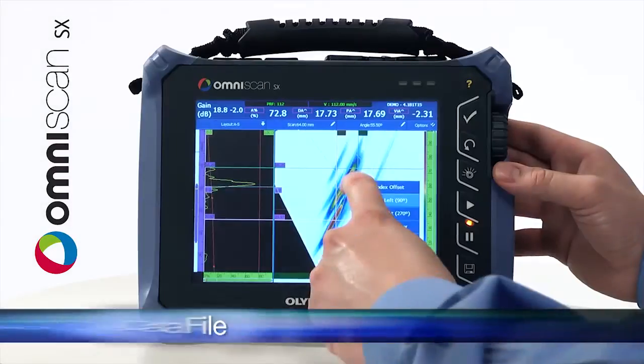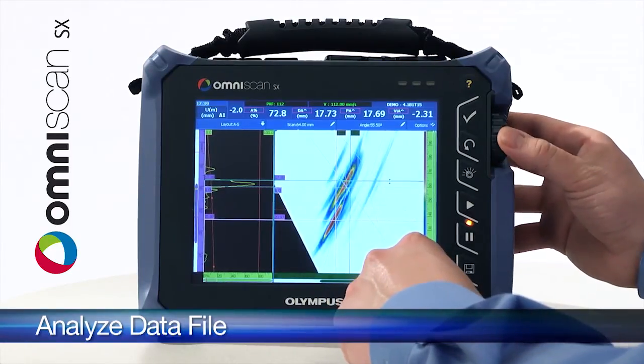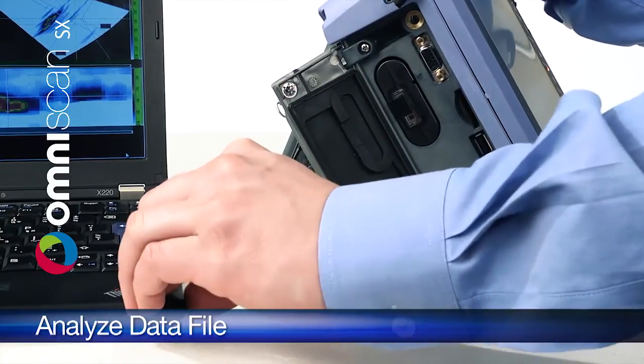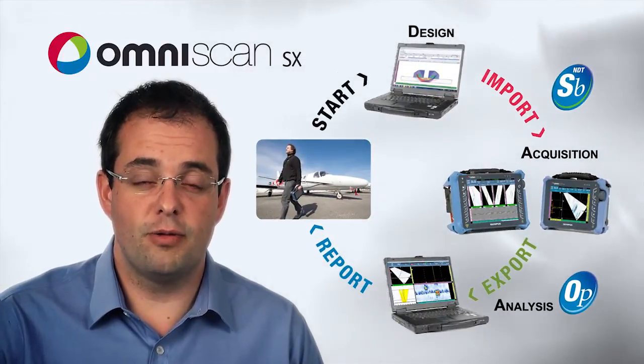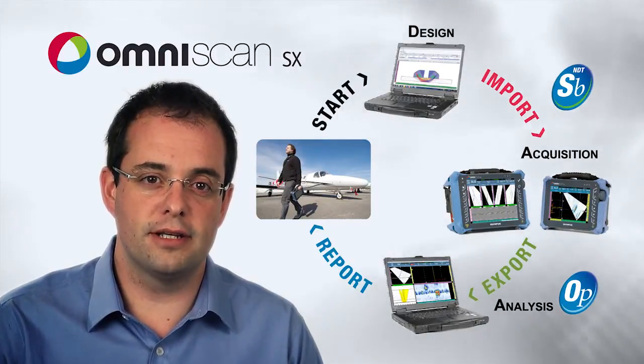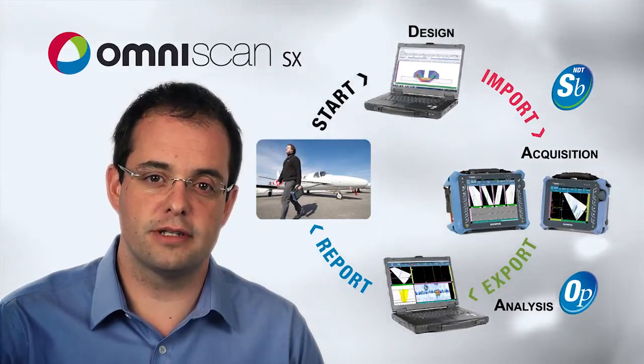After the inspection is complete, the saved data file can be analyzed directly on the unit or on a computer using OmniPC or TomoView software. With this optimized workflow, the user can get the job done quickly and efficiently. The OmniScan SX is fully compatible with this workflow for any single group application and is also compatible with our existing solutions and accessories.